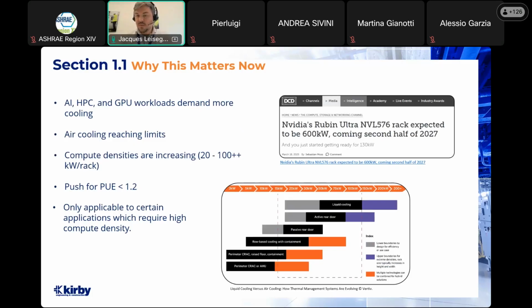As compute demands rise, there's a need for more effective thermal management. Every time we open the news and read about data center cooling and liquid cooling, these rack densities are continuing to rise. You can see there's a snip in there. NVIDIA's Rubin Ultra is expected to be 600 kilowatts per rack. So huge amounts of IT capacity, and as a result, heat rejection needed out of there.